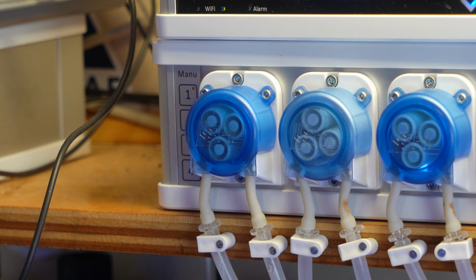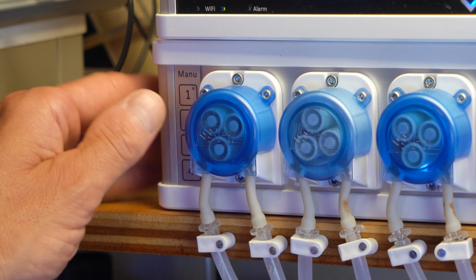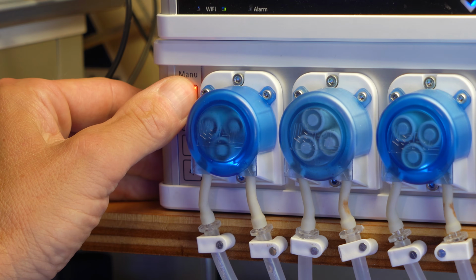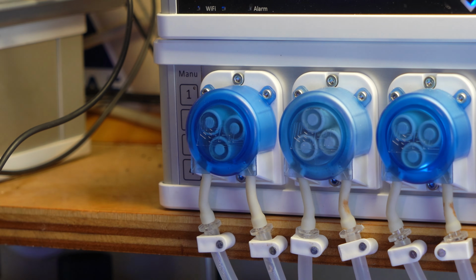The other thing I do on a weekly basis is inspect each of these dosing pump heads just to make sure they're working. I'll manually run them to make sure the rollers are operating the way they should, and the pump is dosing what it should be dosing. I'll check to see if there's any cracks in that cover. Yeah, I'll do that every week.